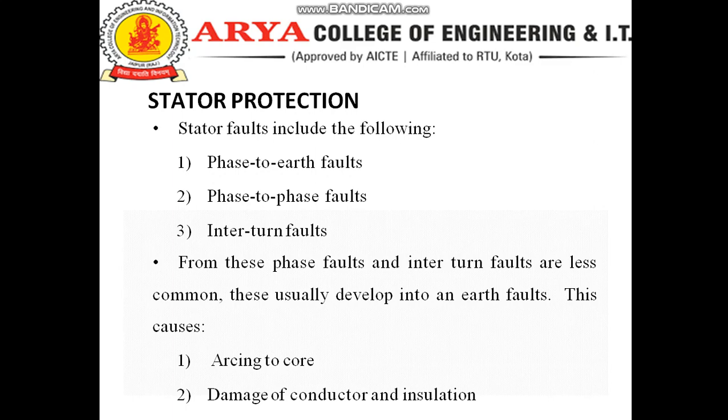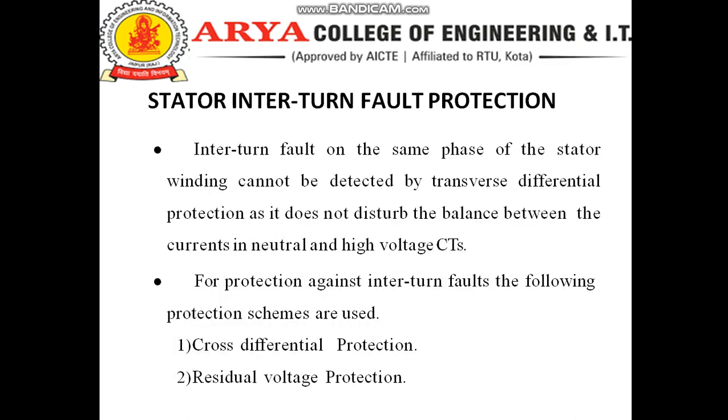Now we discuss the stator protection. The stator faults include the following types of fault: phase to earth fault, phase to phase fault, and interturn faults. From these, phase faults and interturn faults are less common. They usually develop into earth faults. This causes arcing to the core and damage of conductors and insulation.